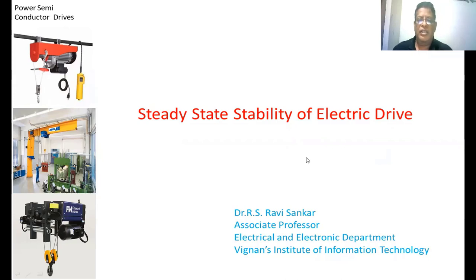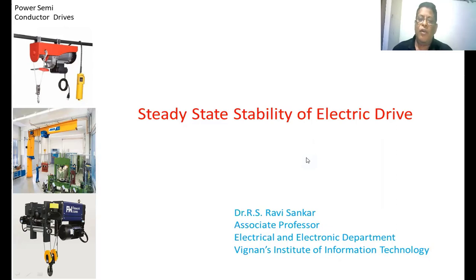Welcome back to the class on steady state stability of an electric drive. In this class we are going to discuss whether the electric drive is stable or not in steady state. Steady state means we have a motor started by giving a supply, we apply some amount of load on the motor so that the motor will be driving the load. The physical meaning of driving that load means the output torque of the motor should be equal to the load torque. That operating point is nothing but steady state.